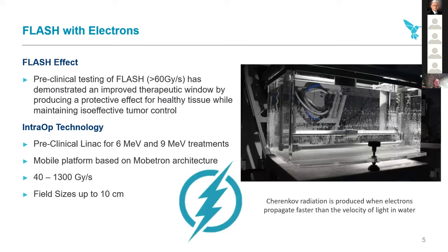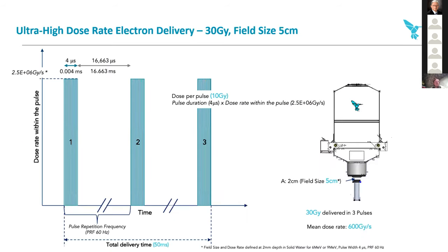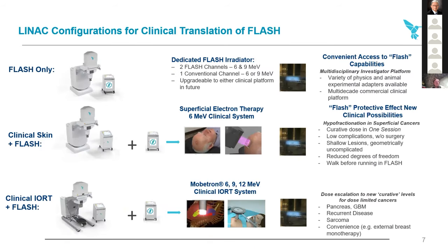Our system offers six and nine MEV treatments with FLASH on a mobile platform, at dose rates up to 1,300 grays per second, as low as 40 grays per second, and field sizes up to 10 centimeters. There's a video demonstrating the system operating in flash mode. The beam structure is a typical linac beam structure — this example shows a four-microsecond pulse with 10 grays in the pulse, so a 30-gray delivery with three pulses. This is a very typical electron linac fine beam structure.